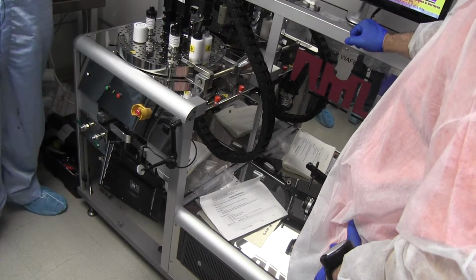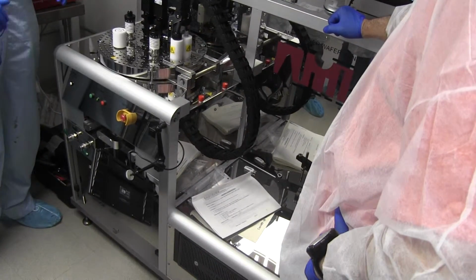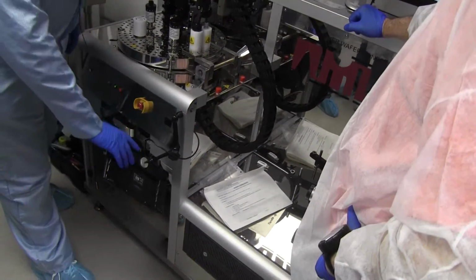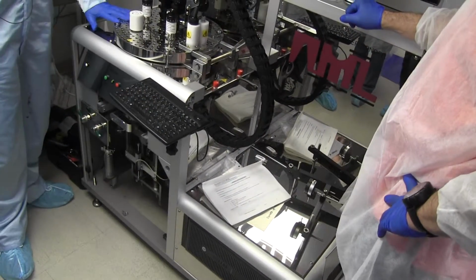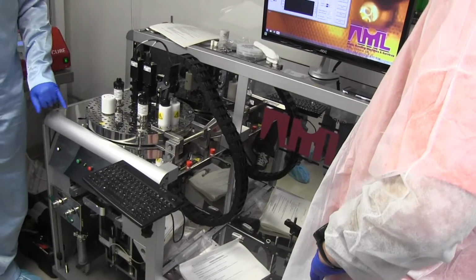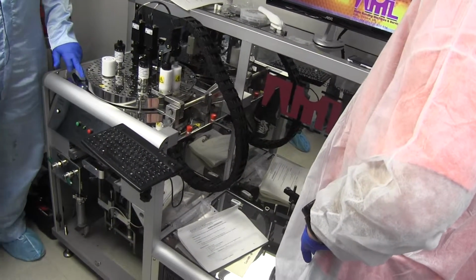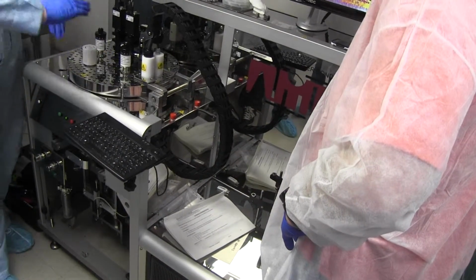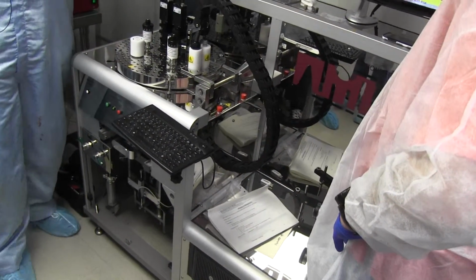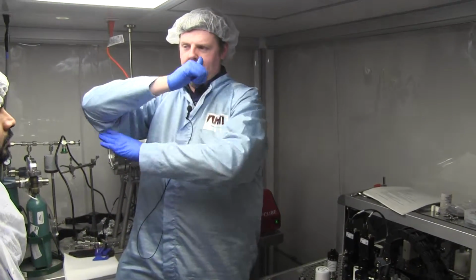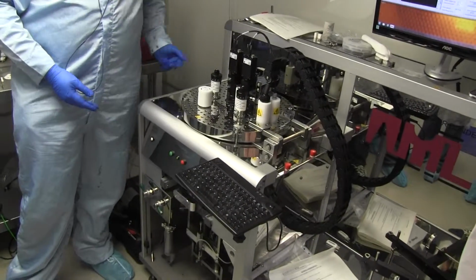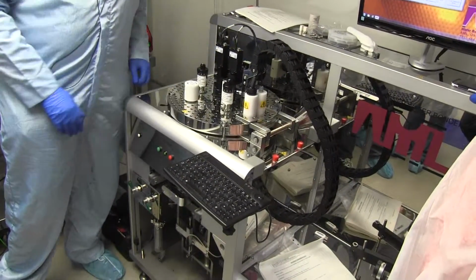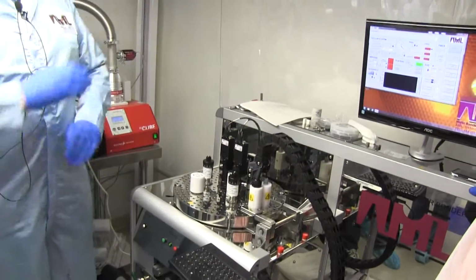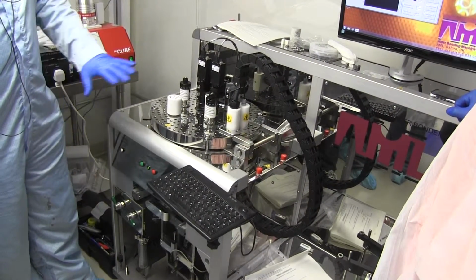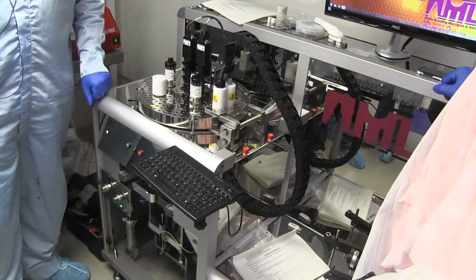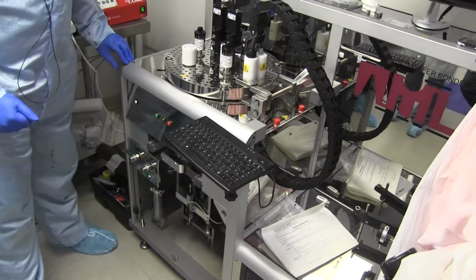I recommend that they're put in all the time. Close the lid, put them in, and then operate, and you're going to have no problems. It's also possible that if they're not in and you try to start pumping down, there might be a slight gap around this edge of the lid, because the lid pivots on the side there. As it comes down, if it hasn't quite contacted on this side, there might be a little gap, and then the chamber will not be able to evacuate, it won't be able to pump. It would be pumping a leak through there. So the clamps help to make sure everything's sat flat and sealed properly before you start pumping out. So I'd recommend that they're used all the time. Good question. Anything else? I think I've covered most of the other things.